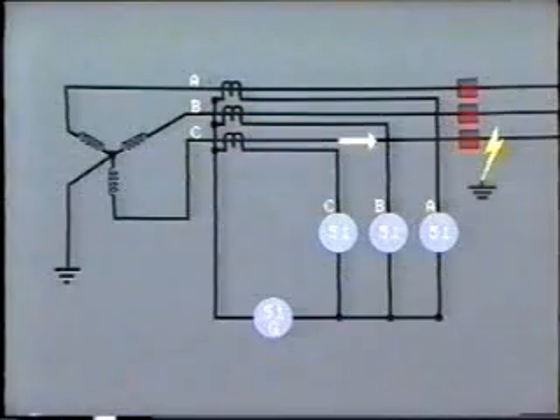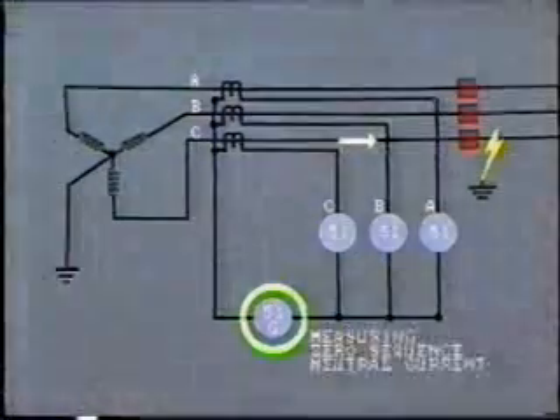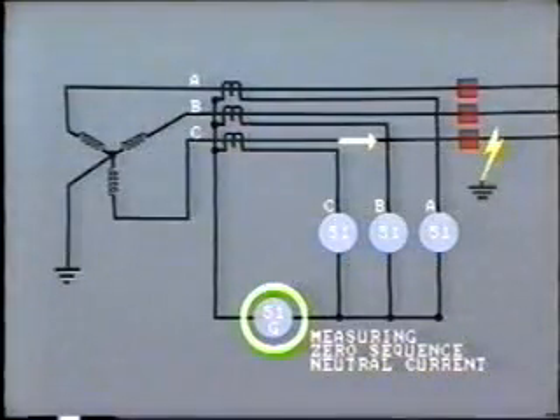The most common form of protection against ground faults on a line is by the use of overcurrent relays, both instantaneous overcurrent and time overcurrent. The ground overcurrent relay is usually connected like this. If a ground fault occurs on one of the lines of the three phases, a high current will flow along the line to feed the fault. The CTs are Y-connected. Therefore, the difference in current flow along the three phases will be registered by the overcurrent relay, which is connected in the common neutral. It is really measuring zero-sequence neutral current.